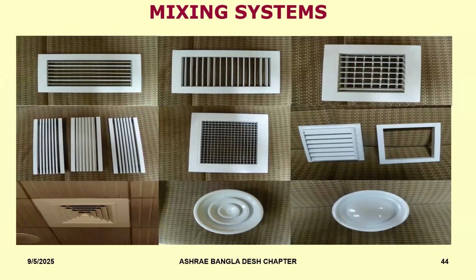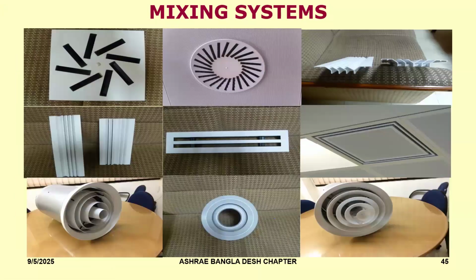To distribute the air in the space, you have various kinds of supply outlets. Here are some which are very common. All of you are familiar with all this. An outlet like this, or this, has got adjustable louvers. The advantage of having these adjustable louvers is that you are able to guide the air and deflect it to places in all corners of the space, so that you are able to get good ventilation effectiveness. As opposed to that, if you use an outlet like this, you're really not able to make any adjustments at the side. These are what you install on the ceiling, like I showed you earlier.